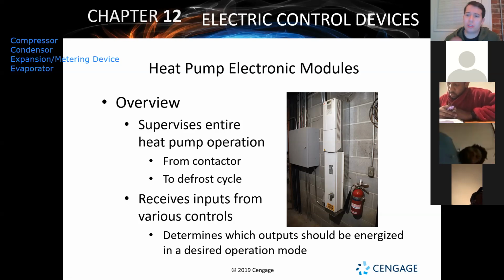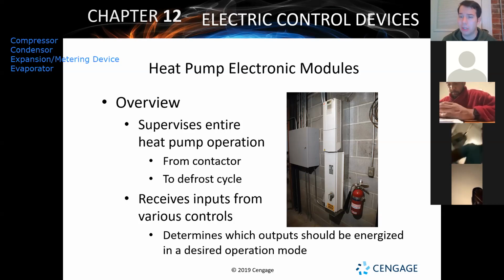So one of the things that happens with this heat pump operating, and you may have seen this at your home or where you live, is that if you've been outside in the wintertime and your heat's running and that outdoor unit is running, you might have seen ice build up on it. It might look like big white ice all over the outside of that outdoor unit, that condenser coil. This is what causes a heat pump to lose efficiency and not be good once it gets to below freezing temperatures, typically, or below 40. And this is what an electronic control module is going to watch out for. It's going to watch for that ice buildup, and when ice builds up, it'll go into a defrost cycle and melt that ice off.